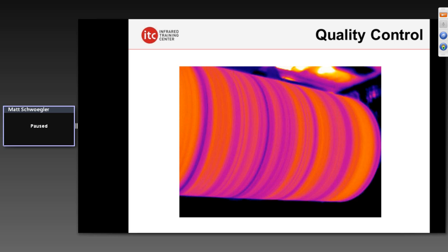In the pulp and paper industry, infrared is used to evaluate the paper product. The darker streaks in the thermal image indicate areas of paper that might still be wet. When surfaces are wet it induces evaporation, which cools the material. We can use a thermal imaging system to see if we've properly dried the product — whether paper towels, toilet paper, or printing paper. Non-uniformity in these patterns indicates the potential presence of moisture within the product.